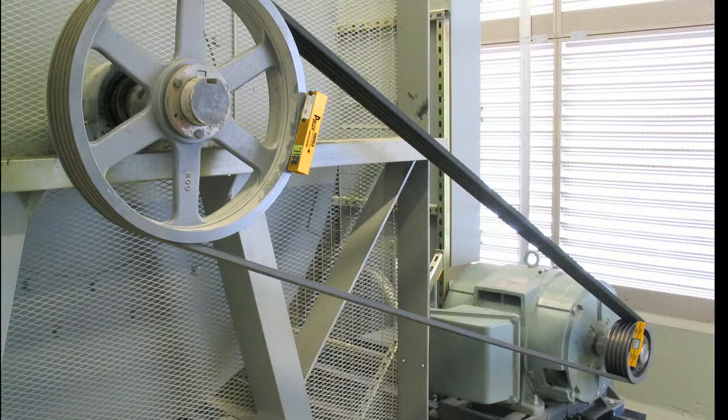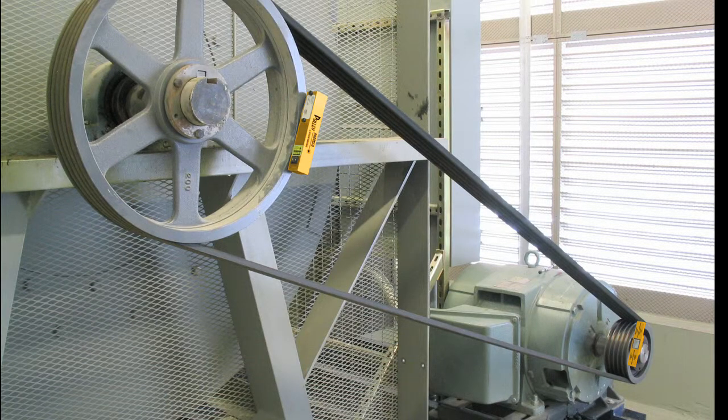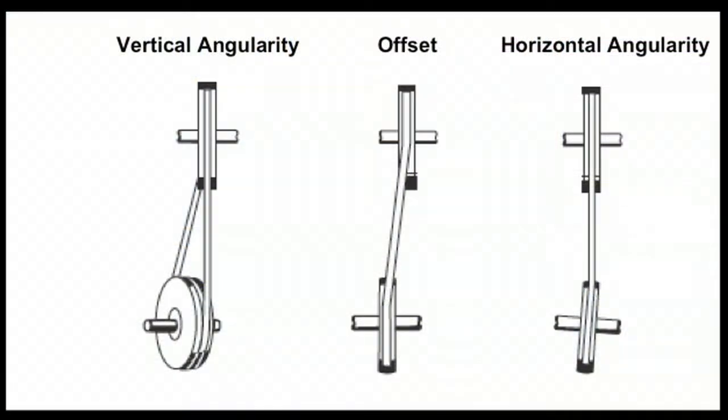In some cases, both pulleys and shafts may need to be adjusted to achieve the desired alignment. There are three basic parameters that describe pulley misalignment. These include vertical angularity, horizontal angularity, and axial offset, and may occur in any combination.